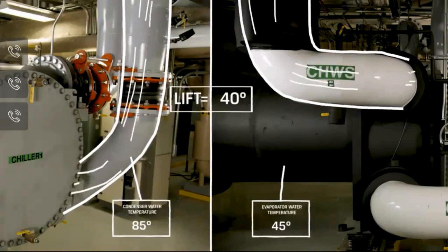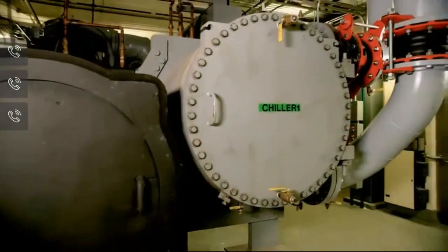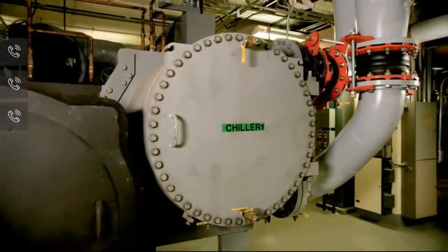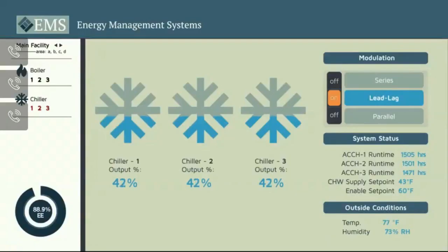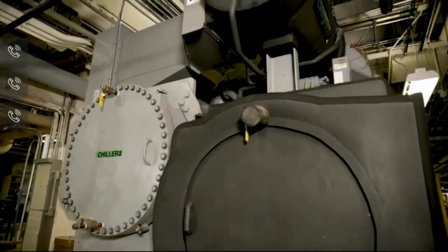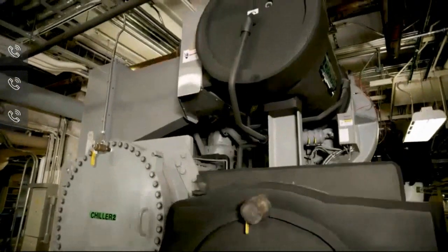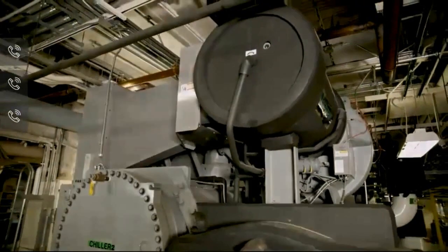Lower lift is better. The most effective way to maximize efficiency in your chiller is with an energy management system, or EMS. An EMS will constantly control, monitor, operate, and alert you to any potential issues with your chiller system. Considering the energy it could save, adding an EMS is definitely worth the investment.